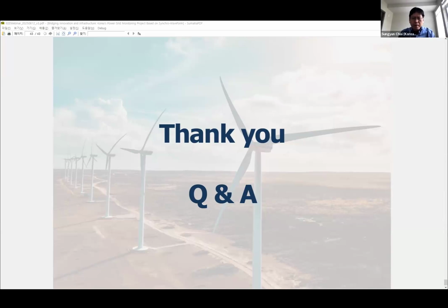That's a good question. Actually, PMU cannot capture high frequency oscillations, so we need to install WMU where needed. Regarding overlapping, I think if an area already has PMU, we don't need to remove it when WMU is installed, because with more data the accuracy increases. Sometimes we still need PMU data, since it has lower resolution than WMU but the data is very light, so sometimes PMU data is also required.